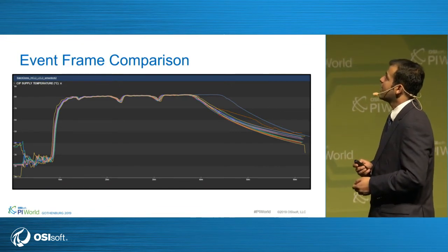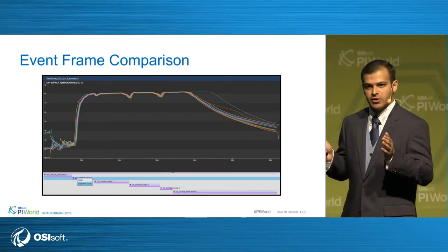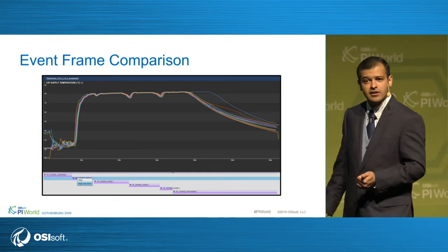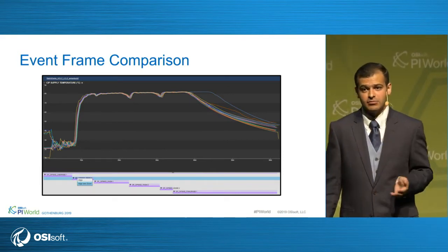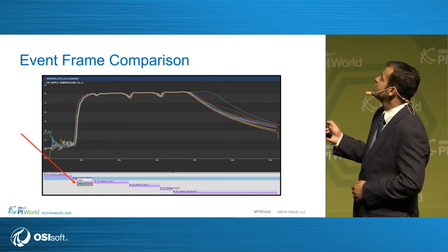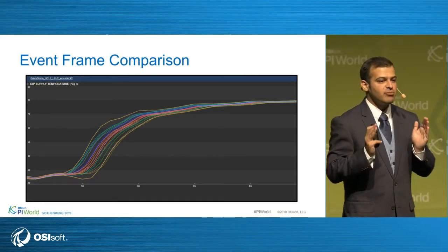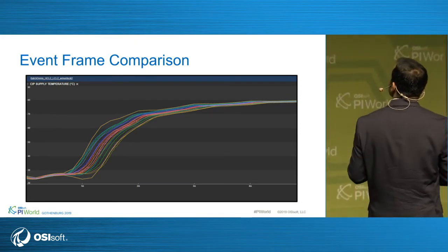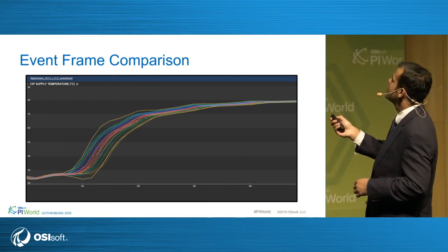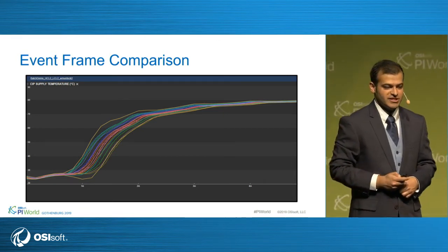So over here, I'm looking at event frames and a lot of child event frames. Let me go and choose a certain period where I have a few child events. So it could be my process, like we were looking at the idle process in my example earlier. We were looking at that process and we had idle time, or let's say where the process was happening. Let's say the process was happening over here. I align and zoom into it. Now I can only see these child event frames within this time range that I'm talking about. And I can very clearly see quickly that most of the things meet my upper and lower limits. There is just this one small deviation around here. And again, I can take a corrective action just based on this information that I received.